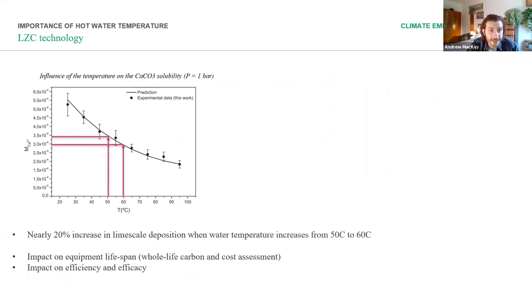And let's not forget about this one. It might be something that is just an annoyance to us, but limescale, other than reducing the lifetime of equipment, also has an impact on the energy consumption. And you can see here that just the 10 degree difference between 50 degree water and 60 degree water gives you a 20% increase in the limescale deposition.